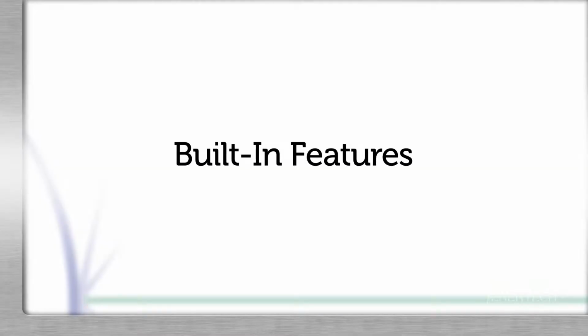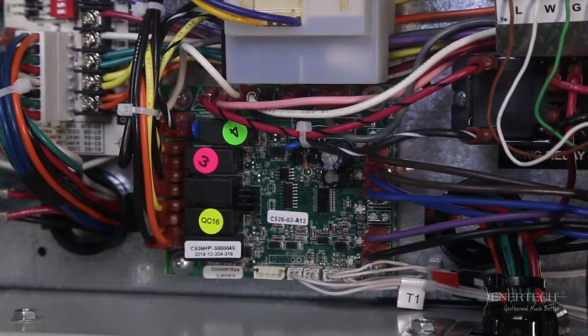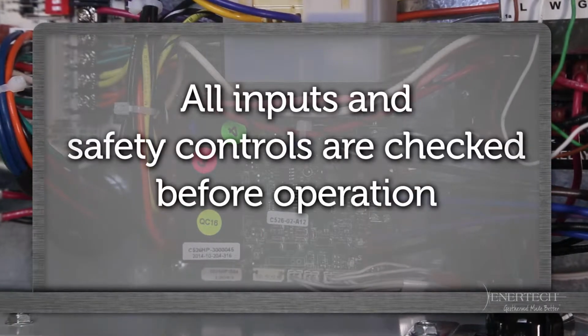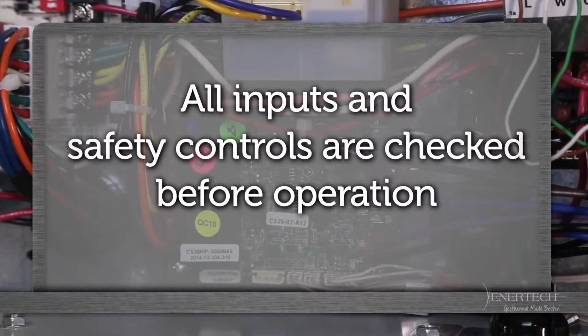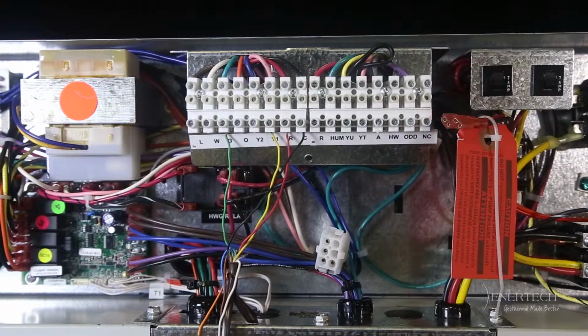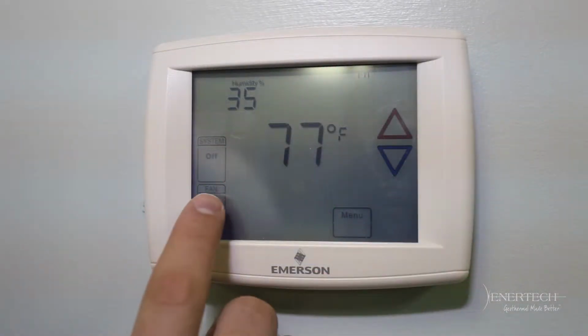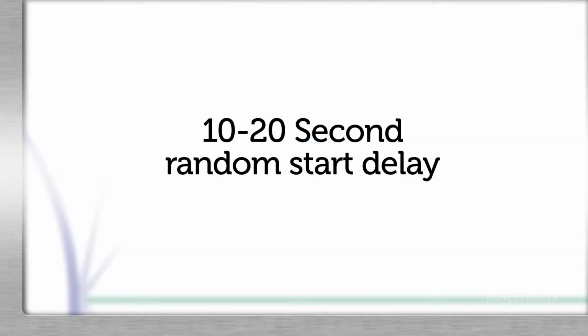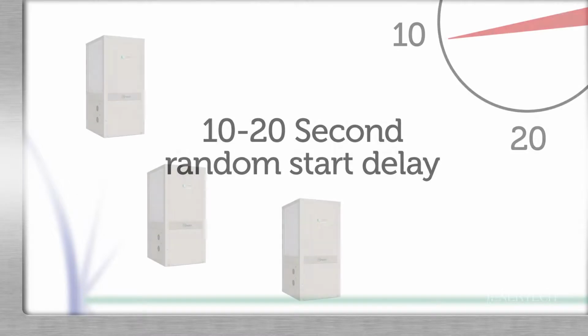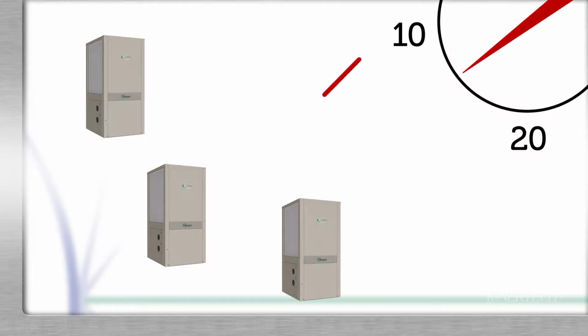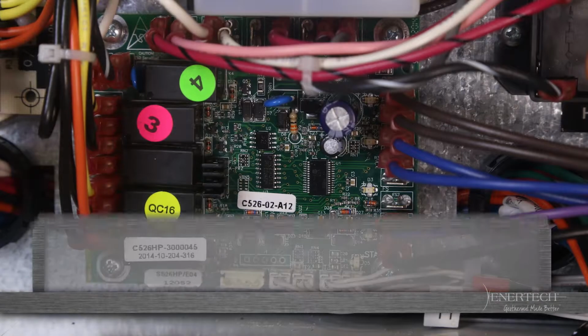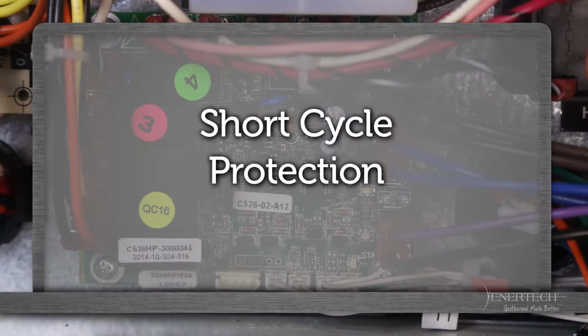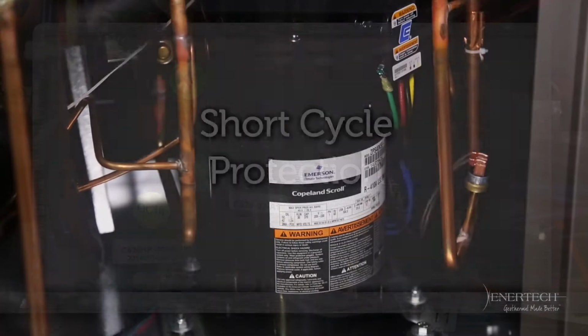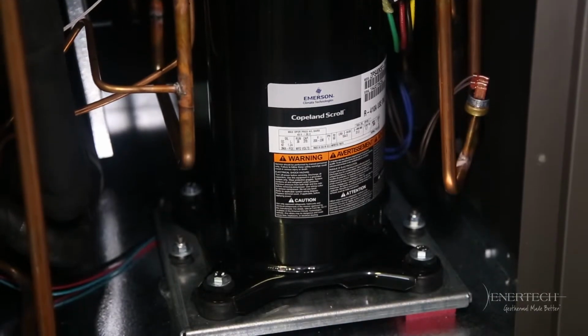Next, we'll discuss the built-in features of the boards. The unit will not operate until all the inputs and safety controls are checked for normal conditions. The controls are checked quickly in the blink of an eye when there is a call for heat or cool. A 10 to 20 second random start delay is added at power up and whenever a Y1 call is received at the unit. This avoids multiple units from being energized at the same time after power loss or other situations. Standard in the control is a built-in 5-minute anti-short cycle timer. The delay provides short cycle protection of the compressor.